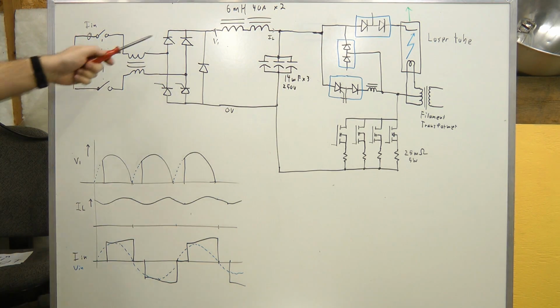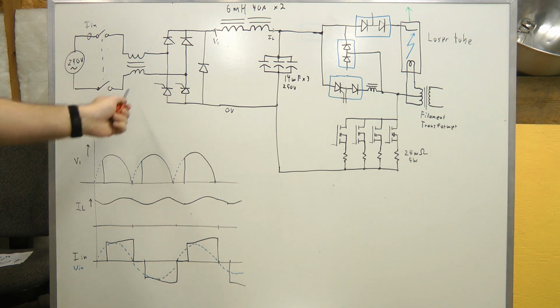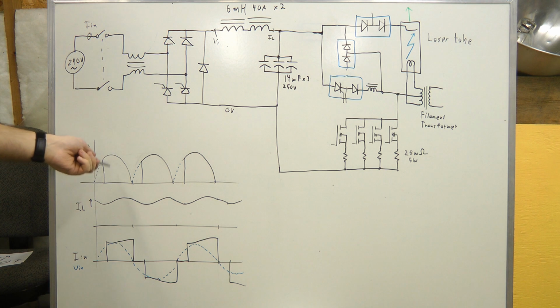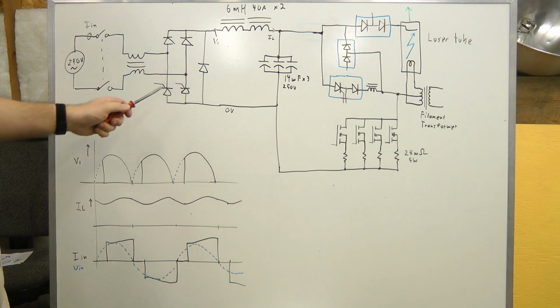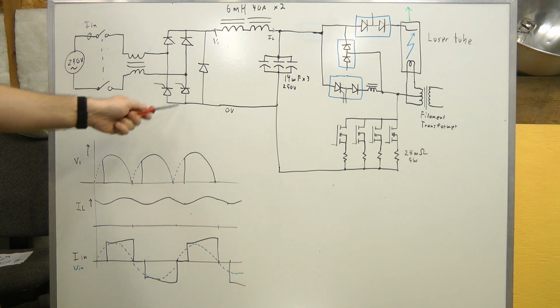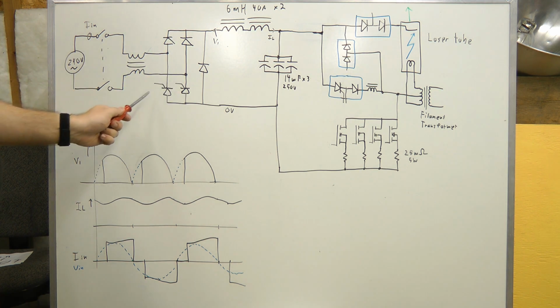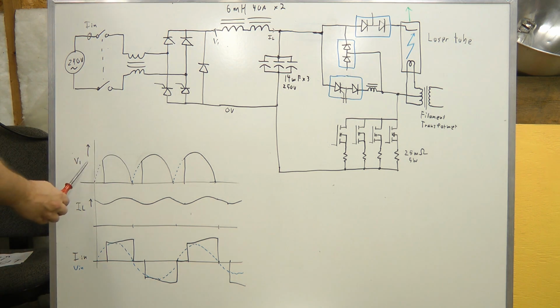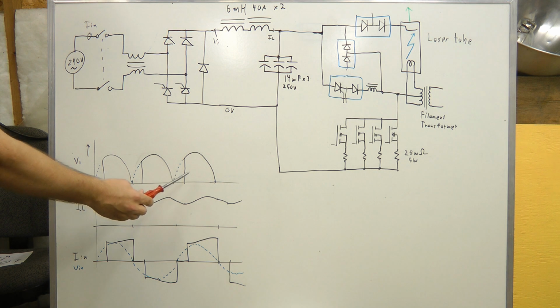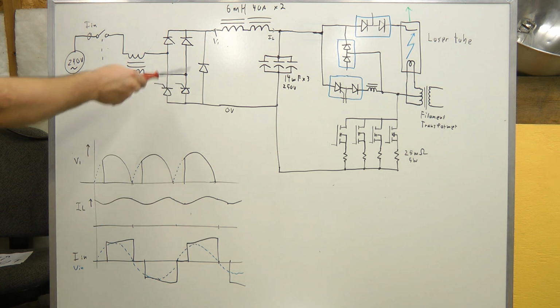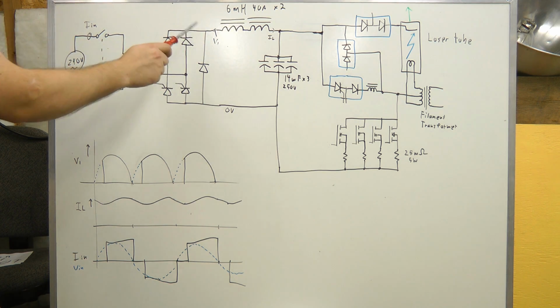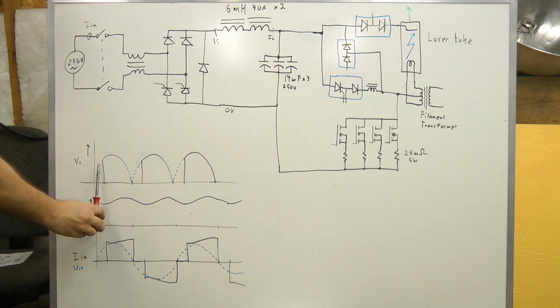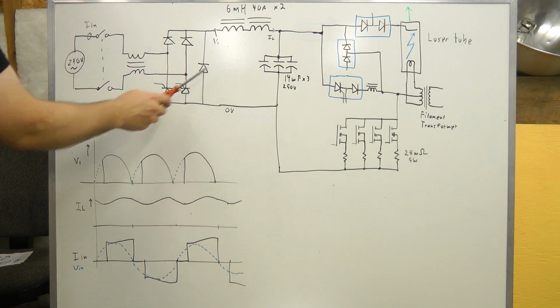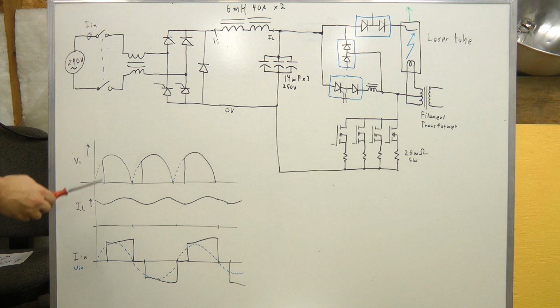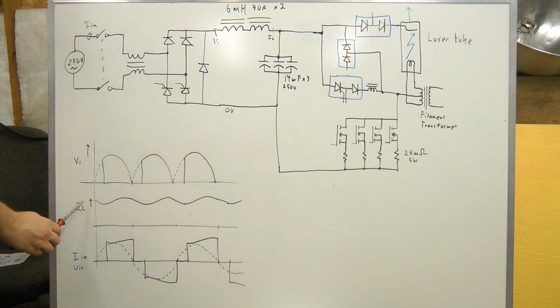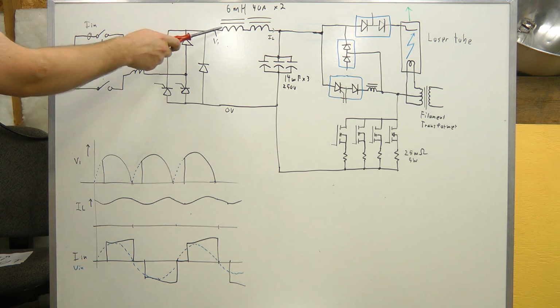So what it's basically doing is pulse width modulating the 120 hertz sine wave. Instead of a buck converter normally running at many kilohertz, this one runs at basically mains frequency. And I initially thought this was just a diode bridge here, but I missed that these are actually SCRs. And these are used to phase shift the rectified sine wave, and you just adjust the phase shift to adjust the average DC voltage across the inductor, and the inductor then filters out the current. So yeah, you'd move this edge, with a feedback loop, to adjust your voltage on the DC bus, and the current will stay relatively constant during the cycle because of these inductors here.